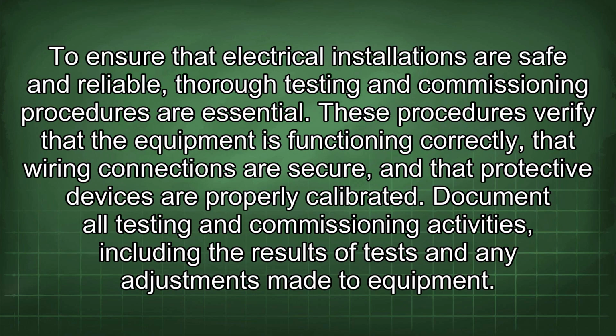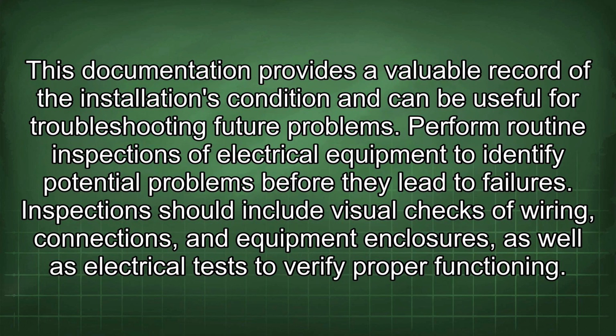To ensure that electrical installations are safe and reliable, thorough testing and commissioning procedures are essential. These procedures verify that the equipment is functioning correctly, that wiring connections are secure, and that protective devices are properly calibrated. Document all testing and commissioning activities, including the results of tests and any adjustments made to equipment. This documentation provides a valuable record of the installation's condition and can be useful for troubleshooting future problems.